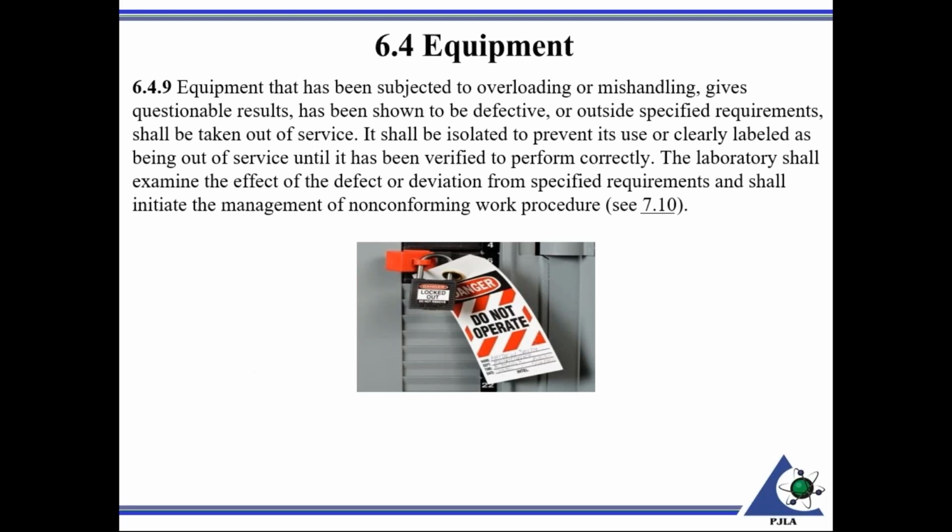6.4.9, defective equipment. If for whatever reason equipment has been subject to overloading, mishandling, or gives questionable results, or is shown to be defective, or perhaps you do have intermediate checks and find that it's outside of specified predetermined limits, it needs to be taken out of service and shall be isolated to prevent its use, or clearly labeled as being out of service until it has been verified to perform correctly.